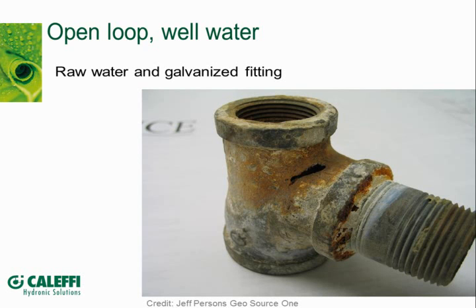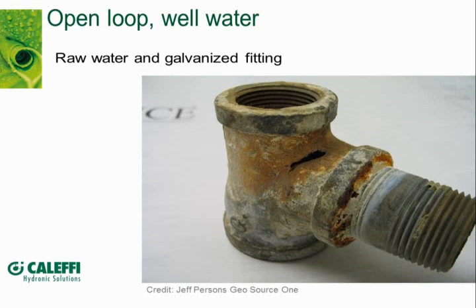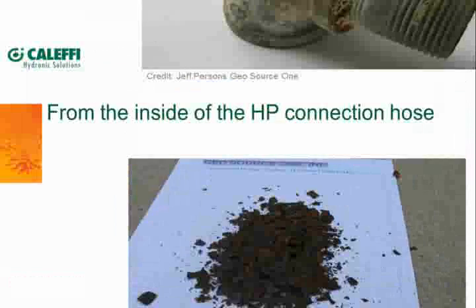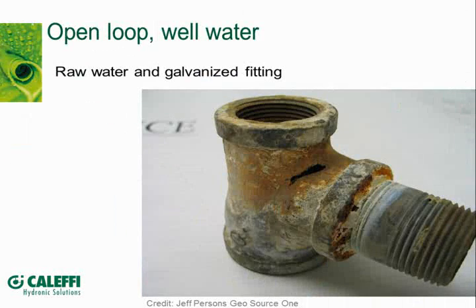And when we talk about open systems that are working with well water, this is a simple galvanized T with a brass nipple inserted into it, so you've got a combination of galvanic corrosion going on there, and you've got the action of raw well water, which literally chewed a hole through it and created quite a bit of water damage in the area where this was located. So you never want to use ferrous metals with raw water supplies. You always want to work with brass, stainless, PVC, CPVC, essentially non-corrosive metals when you're working with raw water.